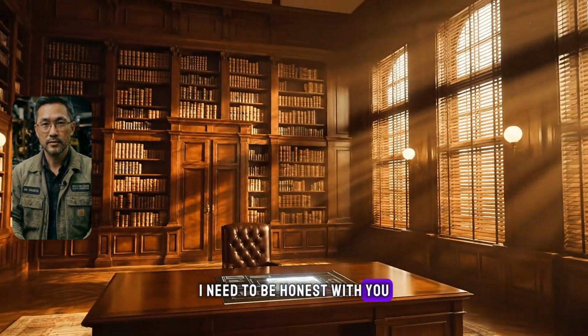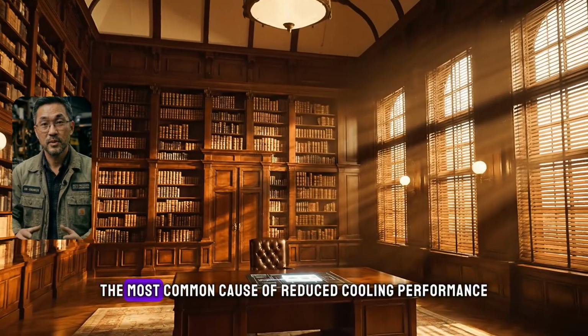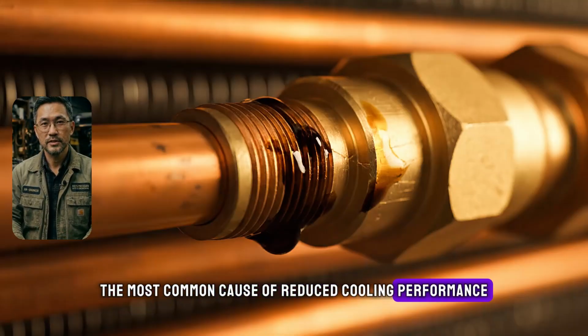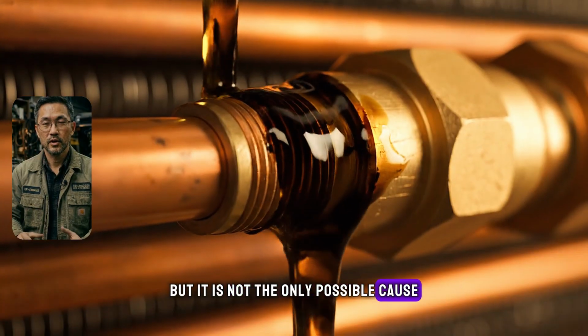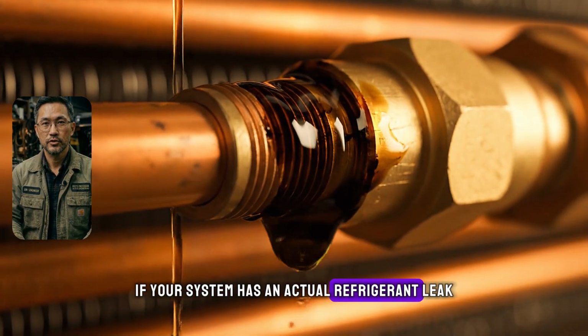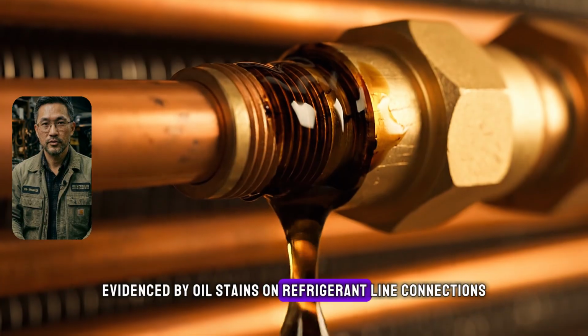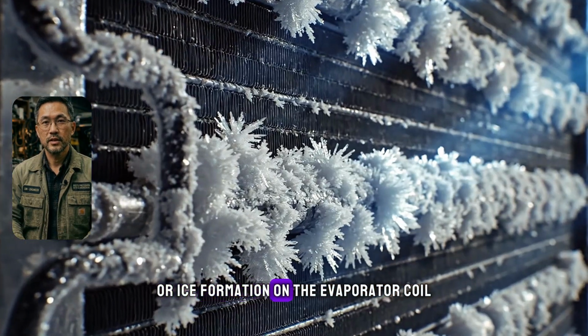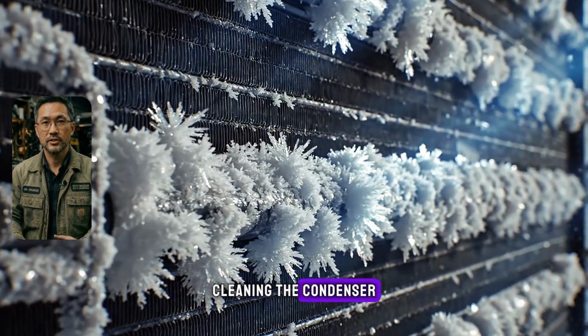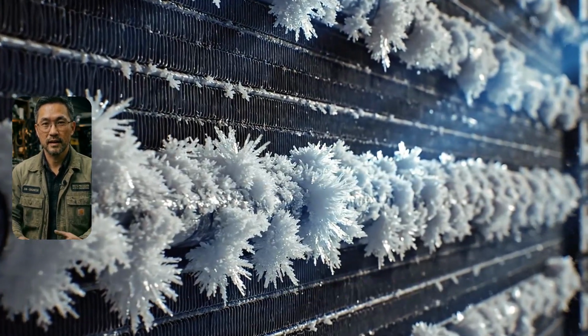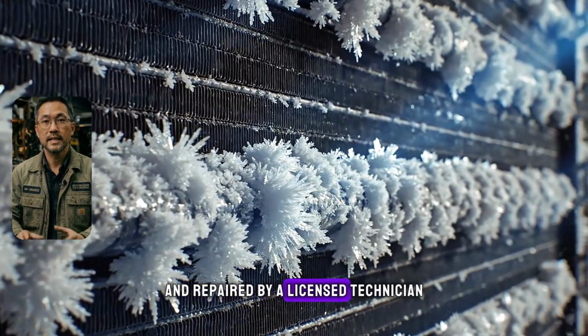I need to be honest with you. Cleaning the condenser coil addresses the most common cause of reduced cooling performance, but it is not the only possible cause. If your system has an actual refrigerant leak, evidenced by oil stains on refrigerant line connections or ice formation on the evaporator coil, cleaning the condenser alone will not restore full performance. The leak must be found and repaired by a licensed technician.